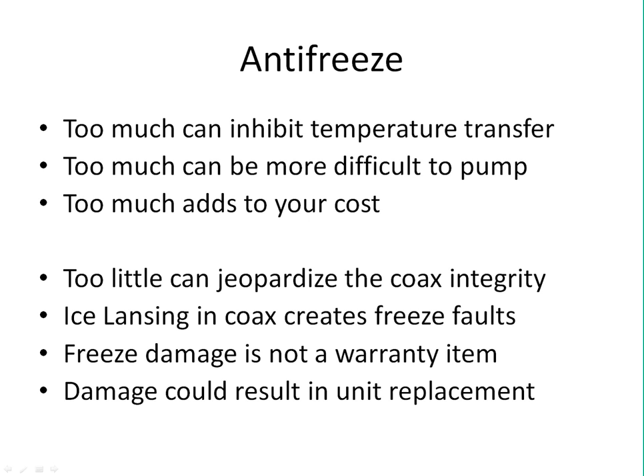And you could, in fact, get a freeze protection fault. Well, once that compressor shuts off and the unit is sitting there, it's going to thaw out because you weren't fully frozen. You were just starting to build up ice crystals or ice particles in there. And what we see is that a guy goes out there and he does his testing and he blames the freeze protection sensor when in fact it probably wasn't the sensor. It was insufficient antifreeze. I see it quite often, actually.